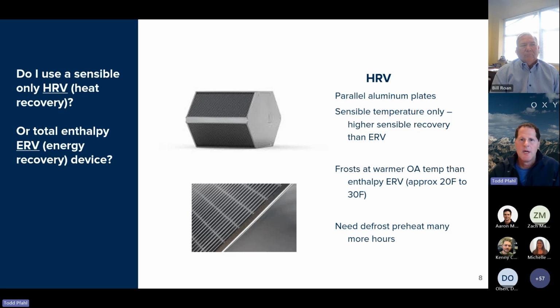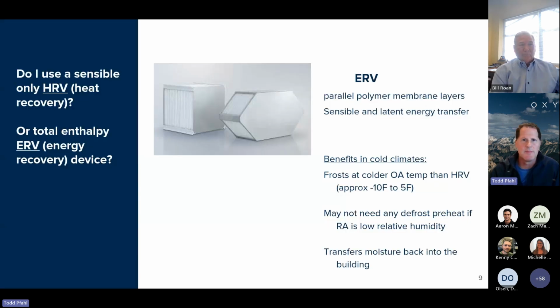However, with cores, you have to worry about frosting in the wintertime. The frosting occurs when your return air starts to freeze. In an HRV, that temperature typically starts to show frosting around 28, 29 degrees. So we need to have a preheater, an electrical device to bump the air up from 0 degrees up to 30 degrees, say, and anytime the air temperature is below that, we need to run it. So it does add energy that we're trying to avoid with these energy recovery systems.